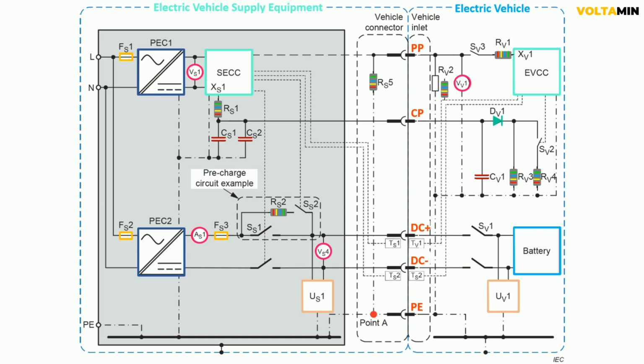PEC1 handles primary power conversion to deliver energy to the EV battery. PEC2 may act as a secondary or auxiliary converter for additional functionality. FS1, FS2, FS3 overcurrent protection devices protect the system against overcurrent events, safeguarding components from damage. RS1, RS2 resistors in EVSE are used in the pre-charge circuit to limit the inrush current during the initial charging stage. CS1, CS2 capacitances in EVSE provide voltage stabilization and filtering in the pre-charge circuit.